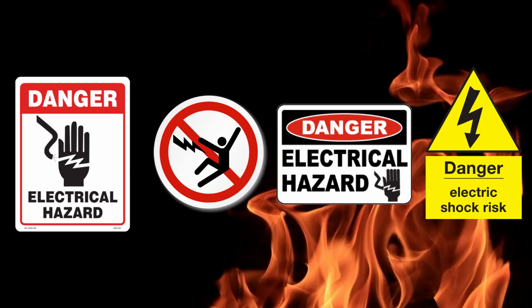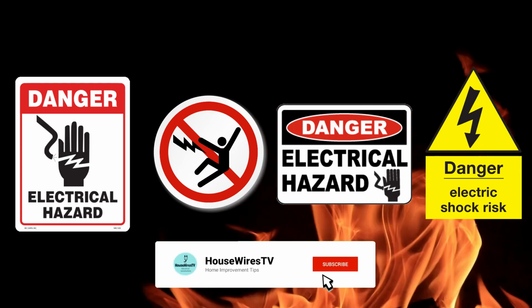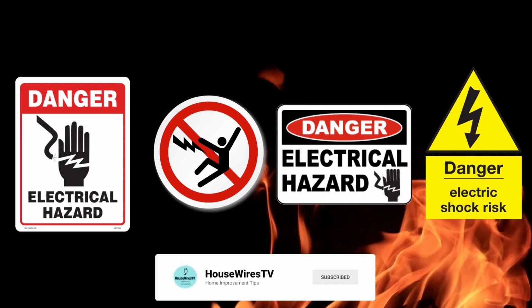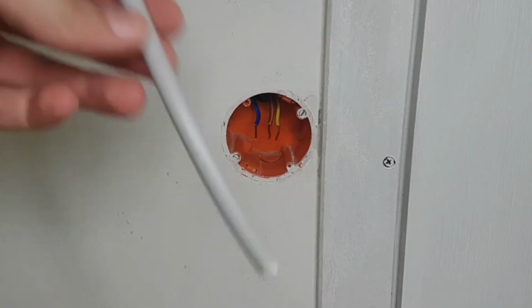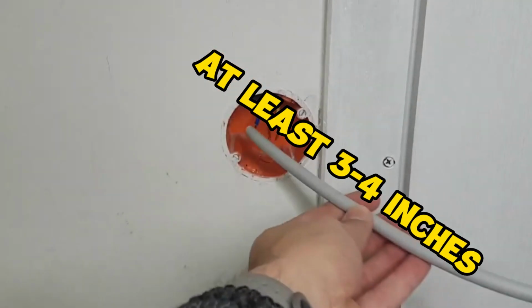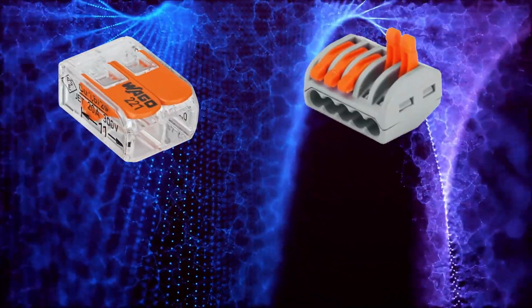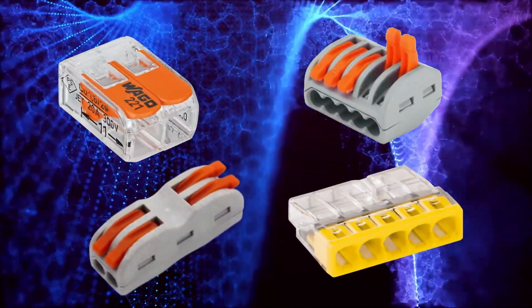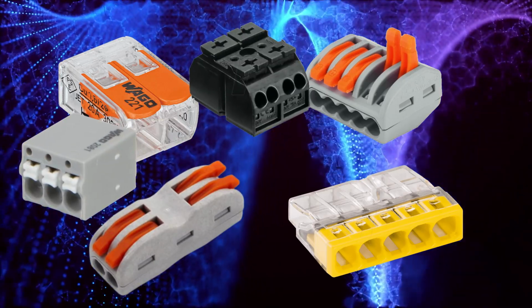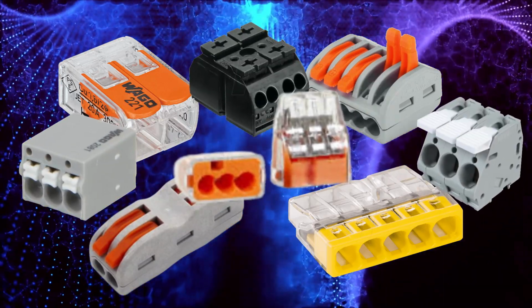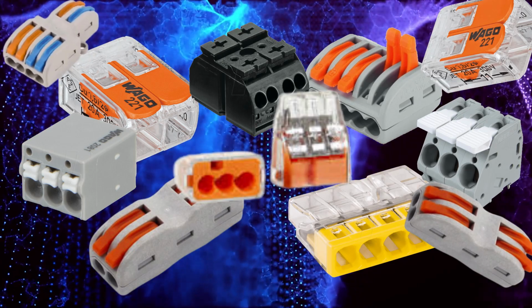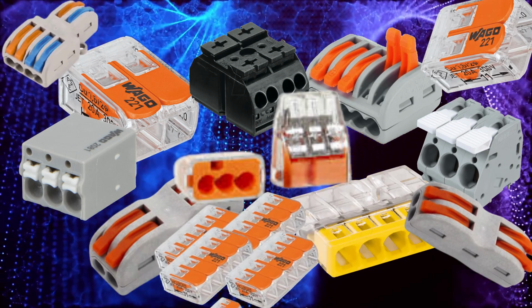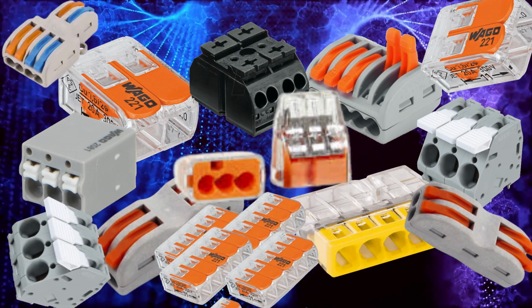This is a common mistake a lot of people make, so leave at least 3 to 4 inches of wire from the wall so you can easily manage your conductors into the junction box or outlet. It is crucial to ensure wires are of sufficient length to maintain safety standards and prevent potential accidents. If you've shortened your wires too much, you can use Wago terminals for an easy and secure connection.